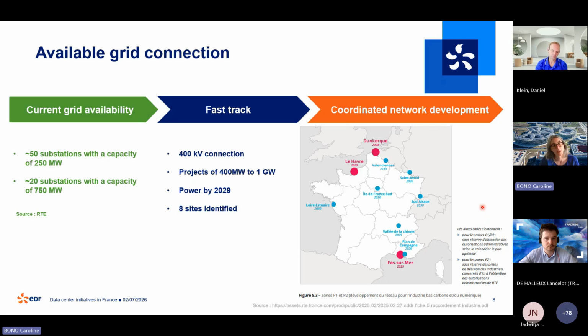Then there was a process validated last year called fast track. The fast track process is for larger projects, between 400 megawatts and up to a gigawatt, connecting to the high voltage 400 kilovolts network, with a guarantee to have power by 2028-2029. They have identified 8 sites in France, and 5 of them have been published. This is a possibility that's been offered, for example, to data centers.